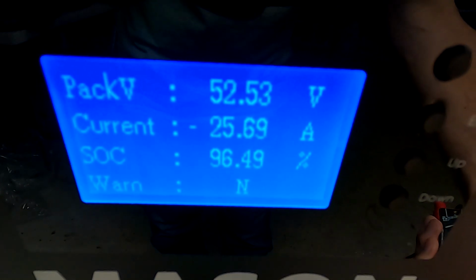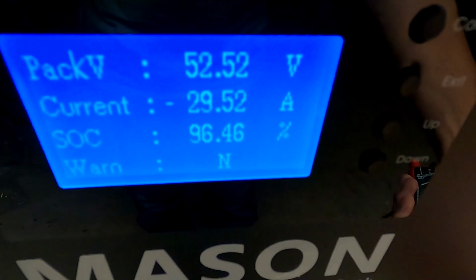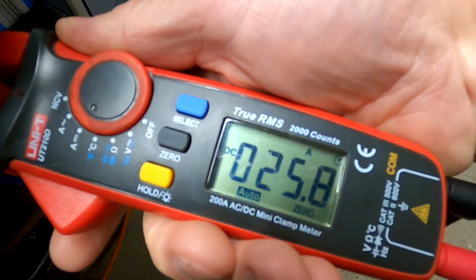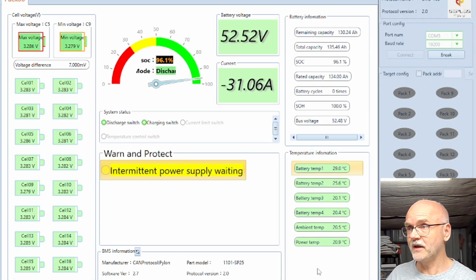So it shows the correct current. There we go, it even goes too high, 30, 25. Well, this could be the case because we are using an inverter and we have DC ripple here, and depending on when the BMS is measuring, it shows different currents, and it does an average of the measurement values it had for the last minute or so. It's just not good. We are at 96% now.